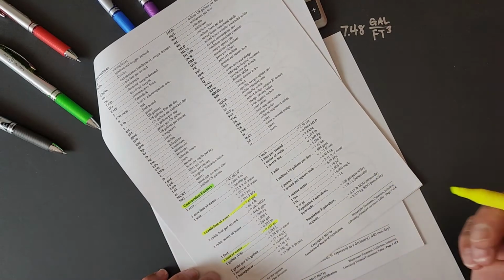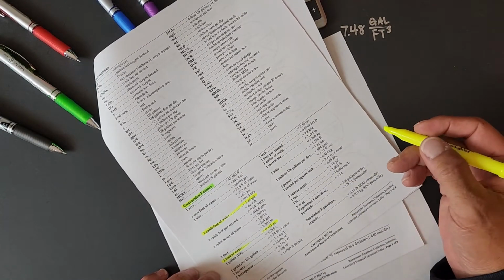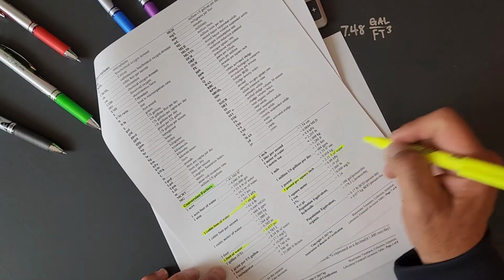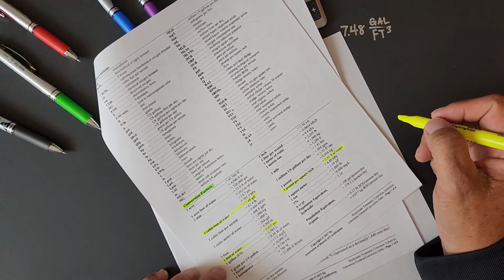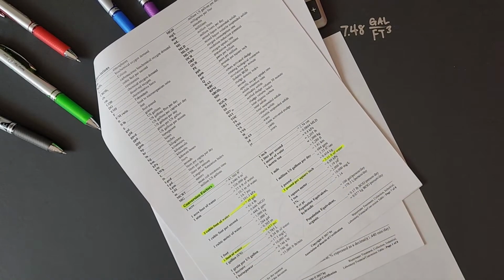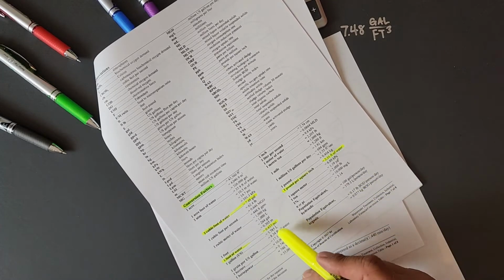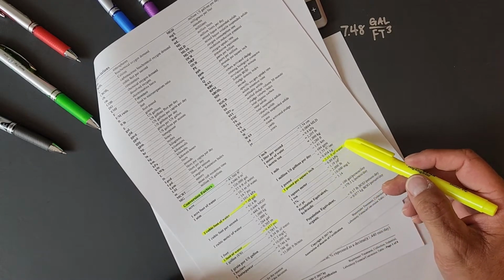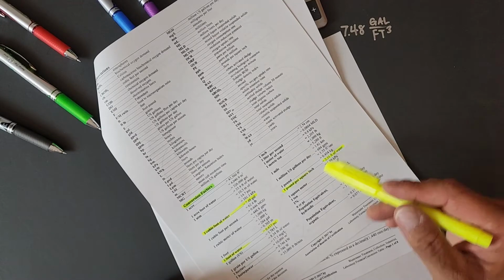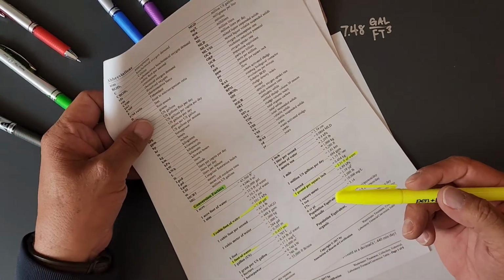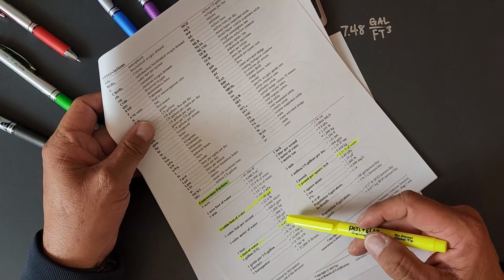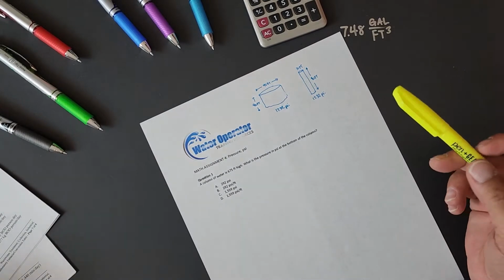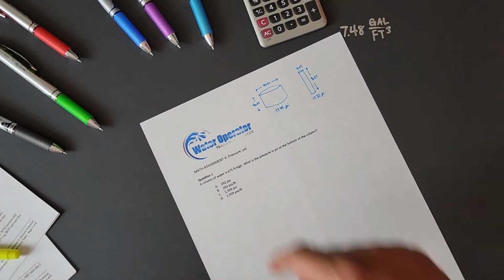How do I know that? Well, let's also note that 1 psi is equal to 2.31 feet of water. Now, this is one of those times when I can use this conversion factor, 0.433, or I can use this 2.31 feet of water per psi. I could use one or the other to make these calculations. I've chosen to stick with one, the 0.433 psi per foot of water. By doing that, I feel like it's less complicated.